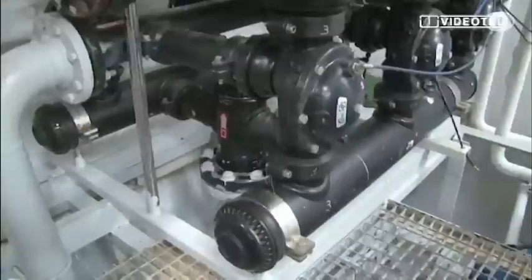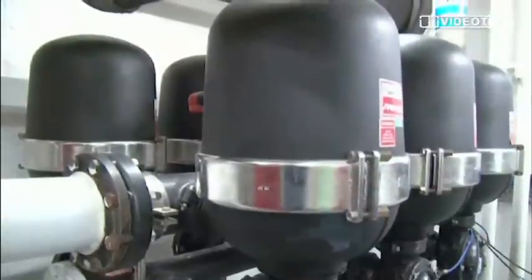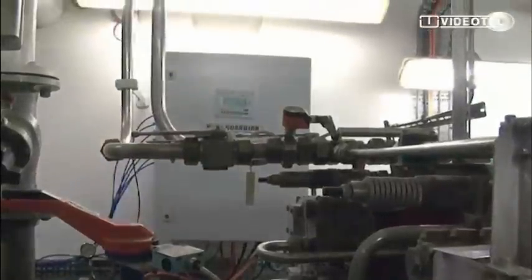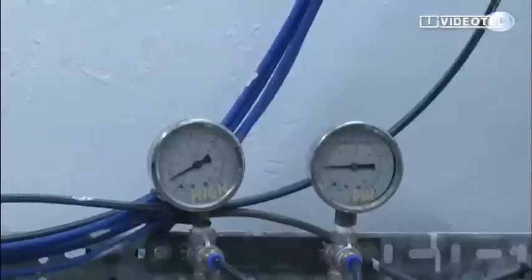When the pump is running, the delivery goes through a battery of six filters which use disk technology, made out of polypropylene. We are using 55 micron size to filter the water. The stacked disk filter technology ensures removal of solids and larger organisms, while the automatic back-flushing allows for continuous flow while keeping the filter elements clean. The system is pretty much self-controlling because the central control panel is automated enough to take care of the back-flushing for the filter, which is very important. There is a control pressure unit which reads the differential pressure from the inlet and outlet, and if the difference is too high, it will do the back-flush automatically. So the filter is actually cleaning itself whenever necessary.